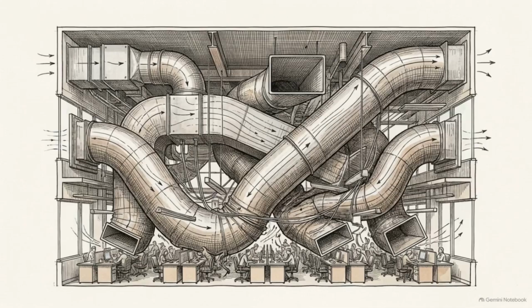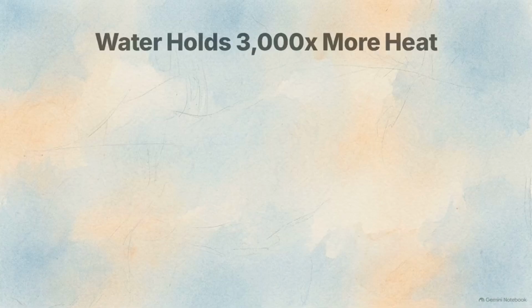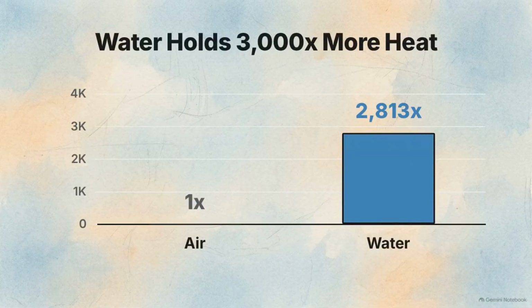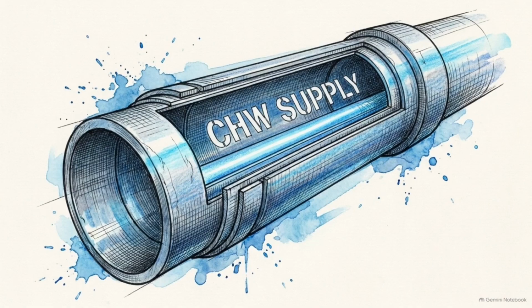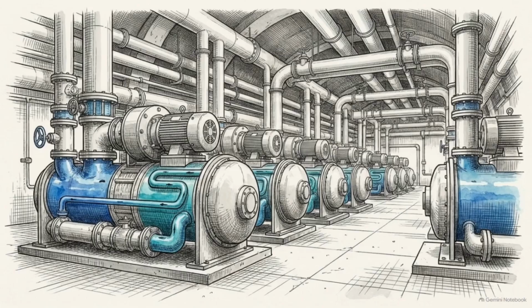To cool a skyscraper this way, the ductwork would have to be so large it would consume the building's usable floor space. Because water can carry over 3,000 times more heat than the same volume of air, industrial-scale cooling requires a transition from air cycling to liquid-based thermal transport. This is the role of the centralized mechanical chiller plant, a specialized system engineered to manage these high-density thermal loads.